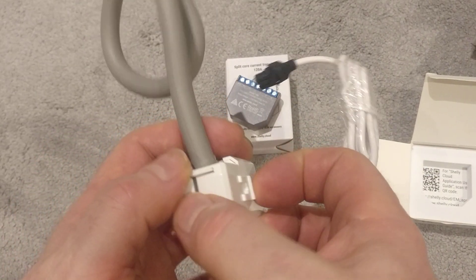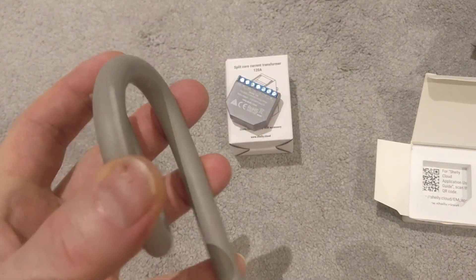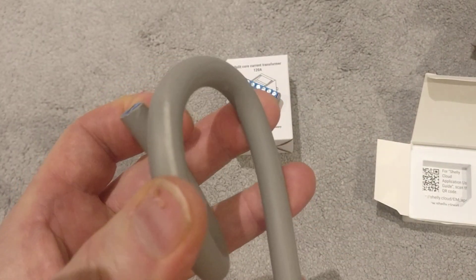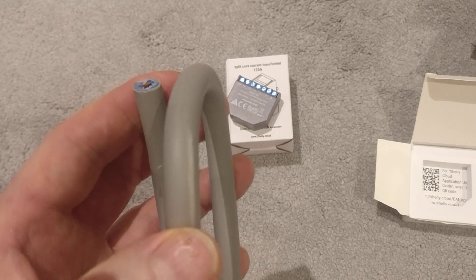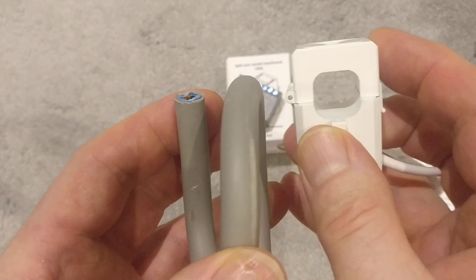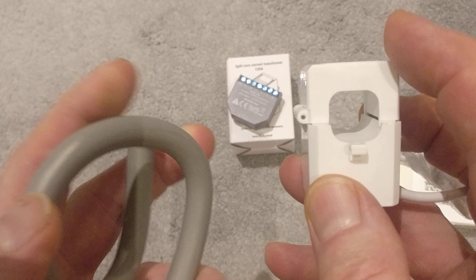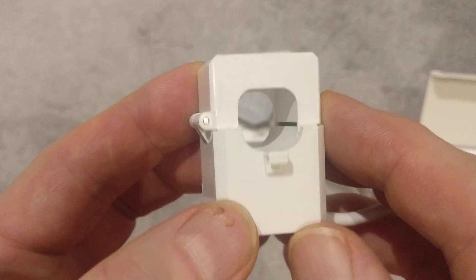The way these work is quite a simple principle. When you pass electricity through a cable, it gives off magnetic flux. If you pass another conductor into that flux, you'll get an induced current. And the induced current is proportional to the current that you're measuring. So inside here is a number of coil windings. As the current flows through this main cable, it will send a current into the coils in here. If you've got a reference voltage — which is 240 — then the current times the reference voltage will give you the power. So nice and simple.